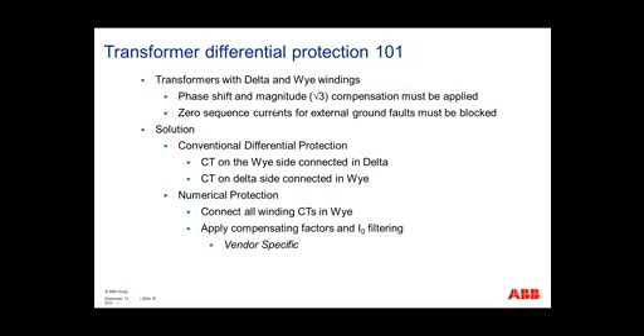So, Transformer Differential Protection 101. Transformers with Delta and Wye connections: you must account for the magnitude square root of 3 compensation, as shown in our previous slides. You also need to account for the fact that the zero sequence currents for any external faults must be blocked. Your solution for conventional differential protection is to connect the CTs on the Y side in Delta, and connect your CTs on your Delta side in Y.